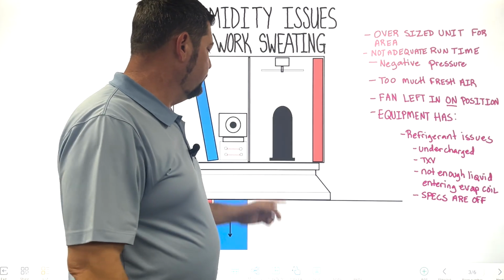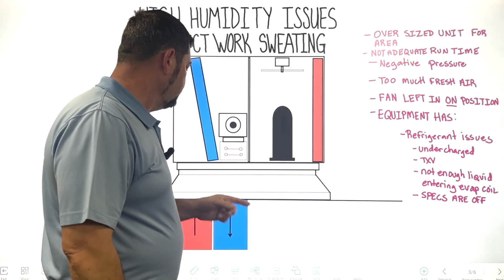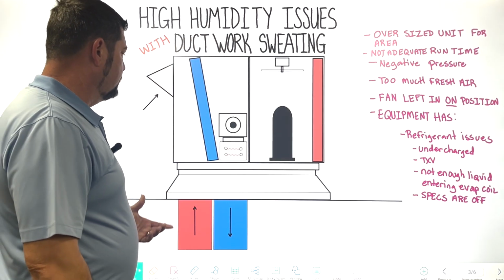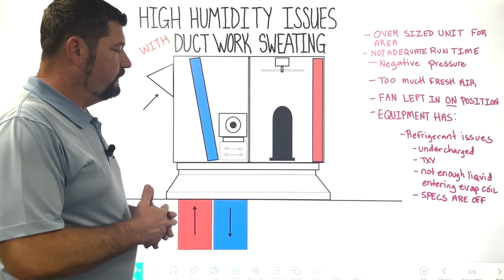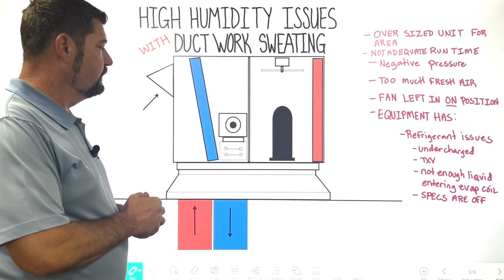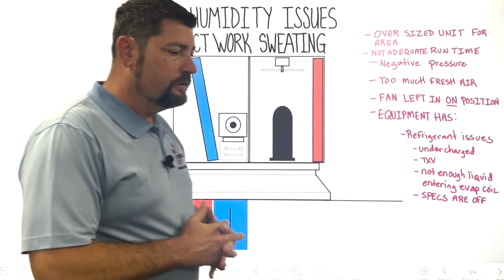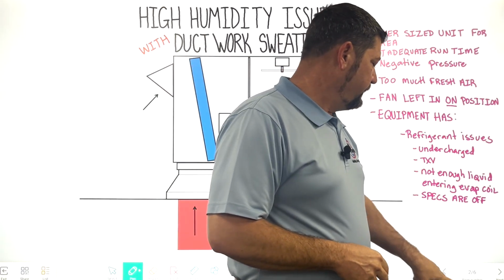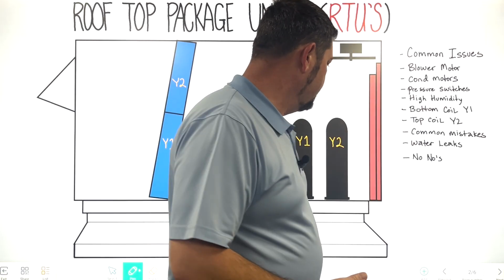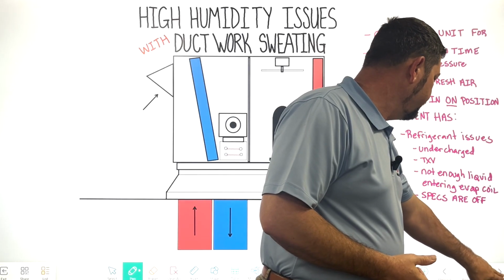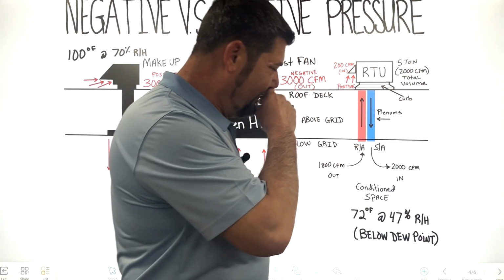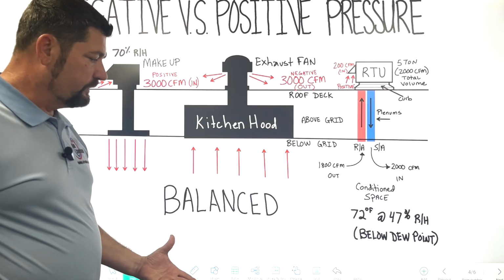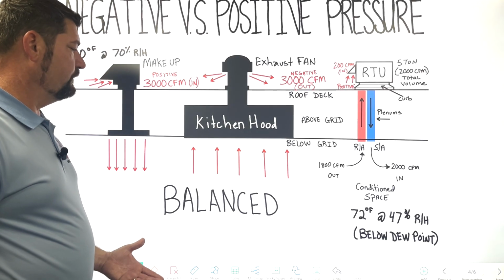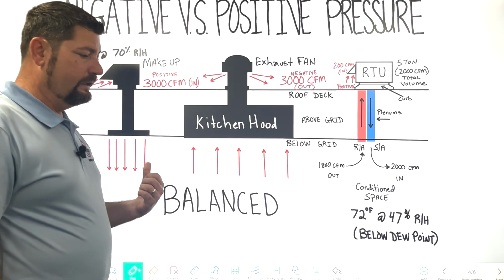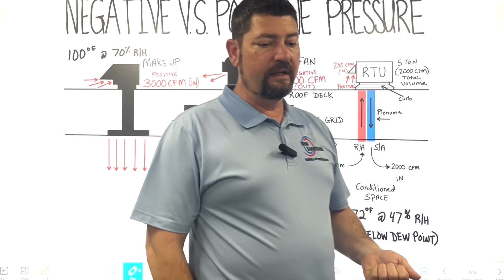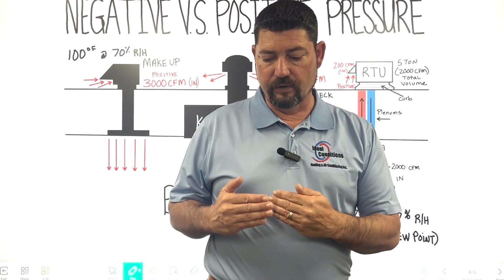Is it the roof leaking? Is it the curb leaking? Is the unit causing a leak? Is there a backed up drain line? What's causing it? And it's very confusing, and a lot of people just missed a lot of things. The first thing you want to inspect, period, is, do you have a negative pressure? And if you have a negative pressure, then your negative pressure is going to be the culprit. And the easiest way to see if you have a negative pressure is you can crack the door open just a little bit.